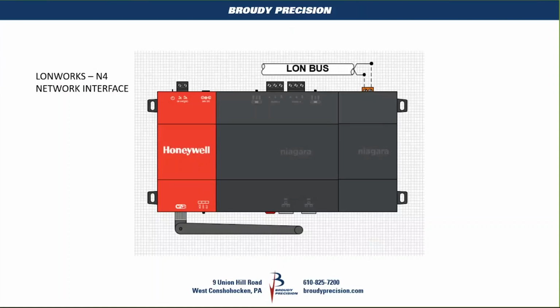One of the things we see in the contractor world is that very often a contractor will get onto a job another contractor installed, and they don't have the station the Spyder program was created in. The building owner says that contractor is no longer on the job, but we created this program for my air handler and I don't like how it's operating. Contractor B enters the scene without the program or station it was created in, and that can be a problem, because if you don't possess the station, what ability do you have to access that existing Spyder?